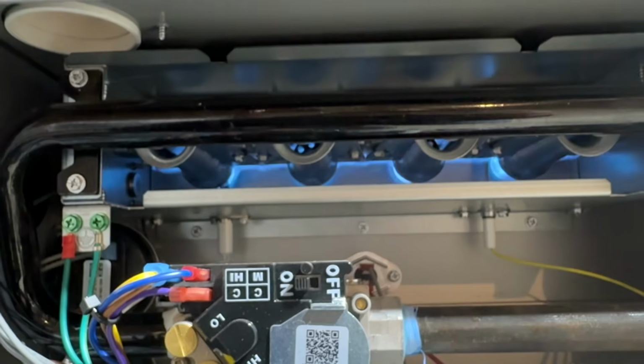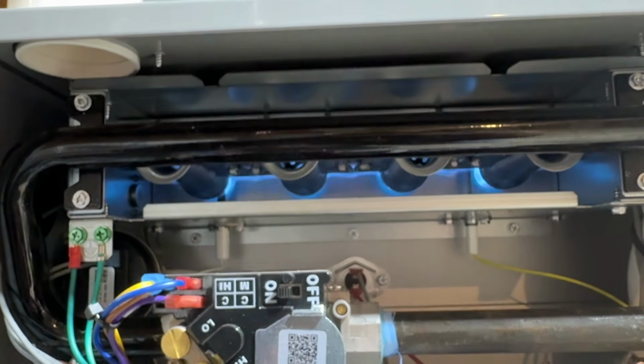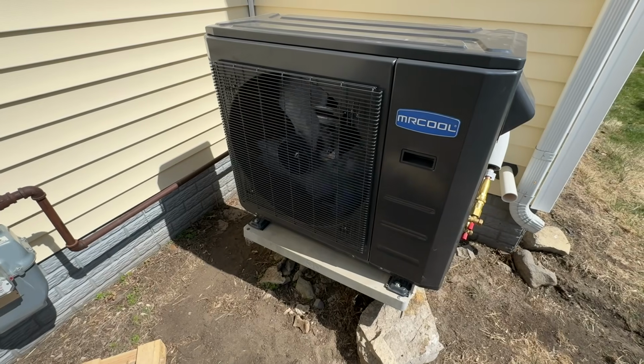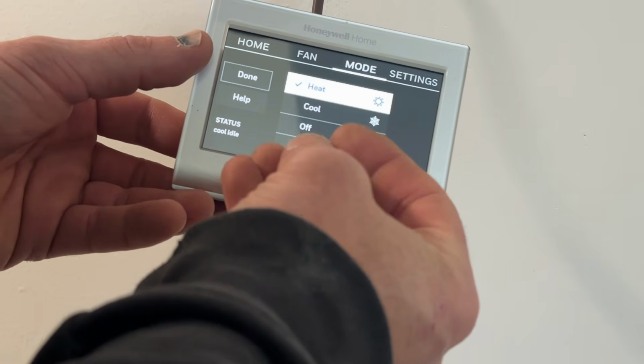This is where some people can get confused. If you just ran cooling and then switched to heat, the system could kick on the auxiliary heat pretty quickly. That's because this coil is still cold or the system is trying to catch up to a big temperature difference. And don't worry, it is completely normal for both the heat pump and the auxiliary heat to run at the same time in these scenarios. As far as the AC, this unit is a one-stage cooling with a modulating inverter, so it will automatically ramp up or down depending on the cooling needs.